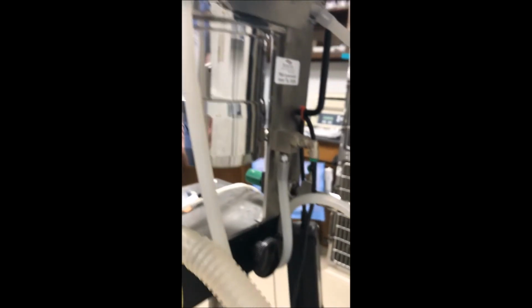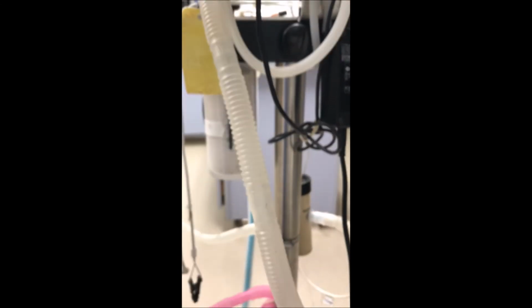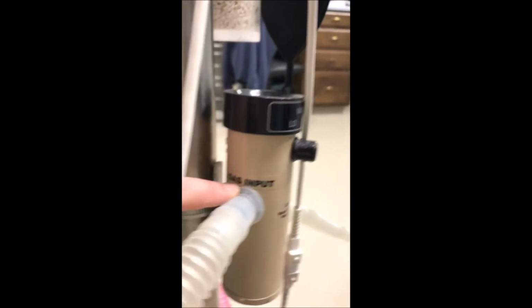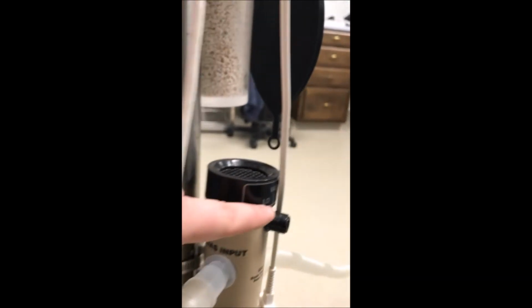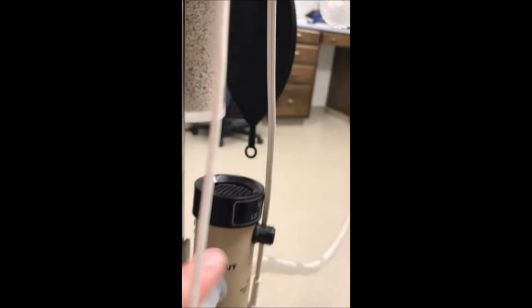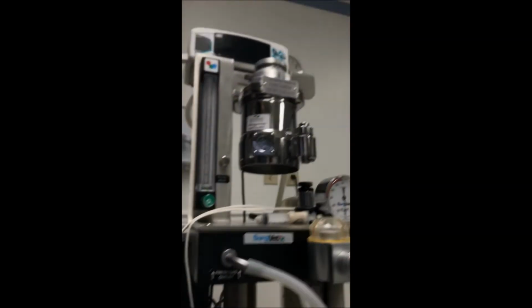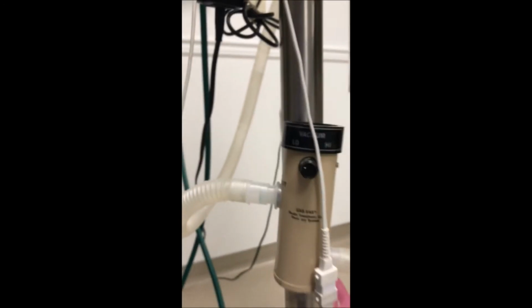On the back side of your pop-off valve, this tube actually connects to our exhaust system. So I'm gonna slowly go around, so I hope I don't make you sick. Our exhaust system starts here, gas inlet. We can have the vacuum set to low or high. We have it set to high. I'm gonna come back around. So it comes through this canister, through this gas vac first, and then it follows the tube up to our exhaust.